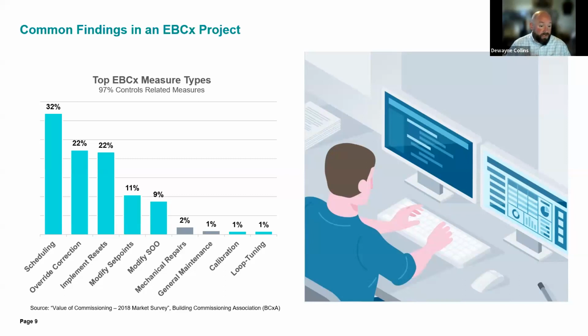We'll go through them: scheduling, override correction, implementing resets, modifying set points, or modifying the sequence of operations. Smaller, more maintenance-related activities like calibration and loop tuning are often suggested through these programs, and there are clearly oftentimes mechanical repairs and general maintenance items as well - but at only 3% of that list, they're a very small portion of what's typically done in existing building commissioning.